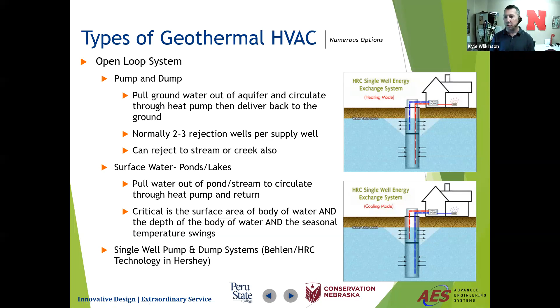So here's another example. What is a system going to serve for design considerations? You can use the water for lots of things. Most commonly, they're used for heat pumps. The heat pumps are able to use that cooler water for heating and then warmer water for cooling. Typical temperatures in the heating, like Vishal said, could be around that 50 degrees or so mark. And then in the summer, they could be designed anywhere from 70 to about 85 degree entering water temperature. The ground generally will do about a 10 degrees difference between the supply and return. So we have to design it for that.